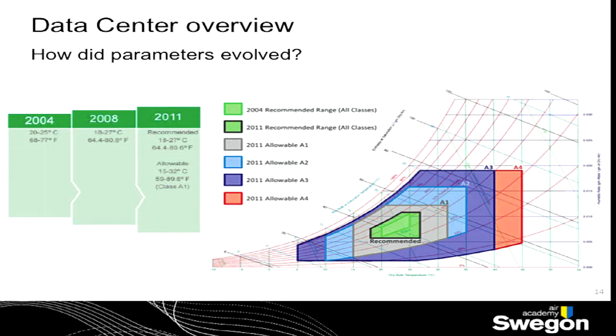But it is quite interesting to have a look at what happened during the last years, from 2004 to 2011, for these levels, because they have increased a lot. So if in 2004 it was 20 to 25, now it is 18 to 27. It seems not so much, but I assure you that we are speaking about 2 degrees on one side and 2 degrees on the other side. It's a huge, let's say, range of temperatures allowed. And if we look at it, the recommended temperatures are higher.